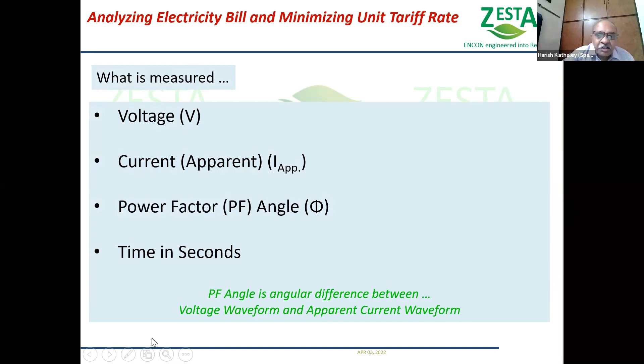Now for power factor, we will understand quickly. We have got resistive loads, inductive loads, capacitive loads, and a combination of all. It is expected that we will maintain the value of 1, not less than 1. If it is less than 1, it should be lagging, not leading. Remember, in another two years, a penalty will be imposed if our average monthly power factor is leading. We will understand this in the next slides.